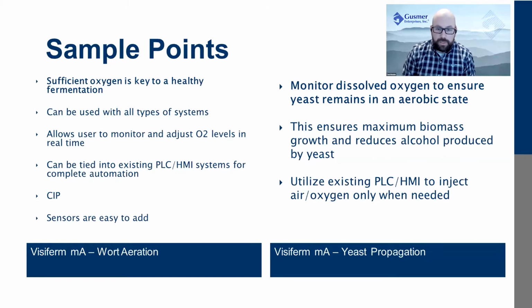The Visiferm can be used with all types of systems, both manual and automatic, allowing you to have real-time numbers during your wort aeration. You can then monitor and adjust oxygen levels during your pump back into your fermenters. Depending on how many production folks are on the call, we've all run out of oxygen tanks before, and sometimes it's not caught immediately.